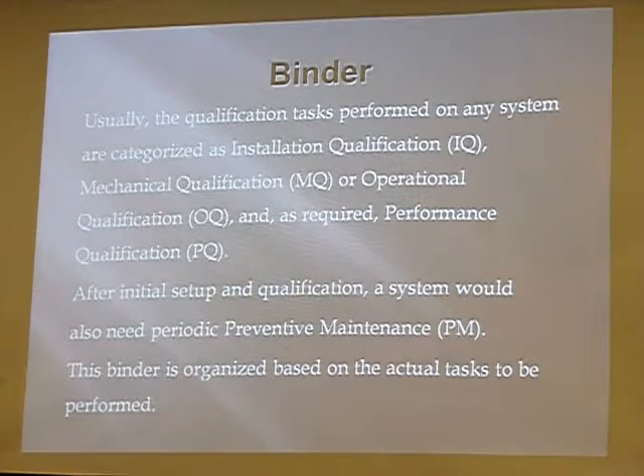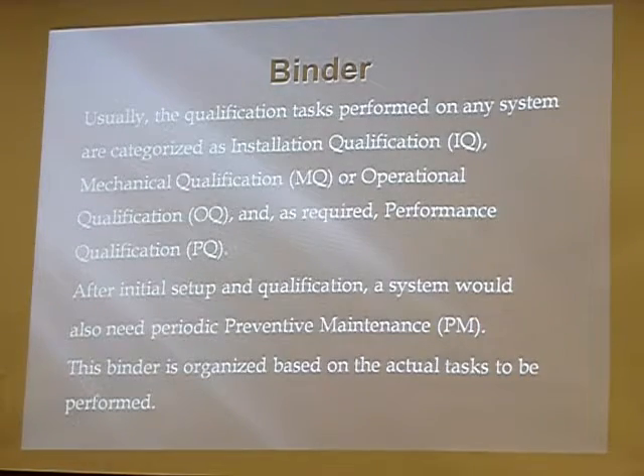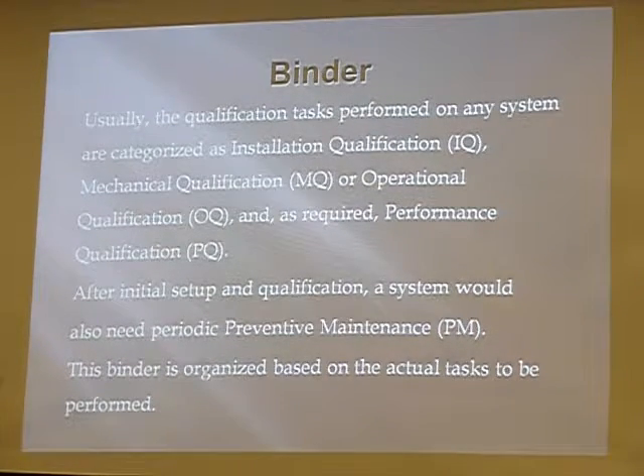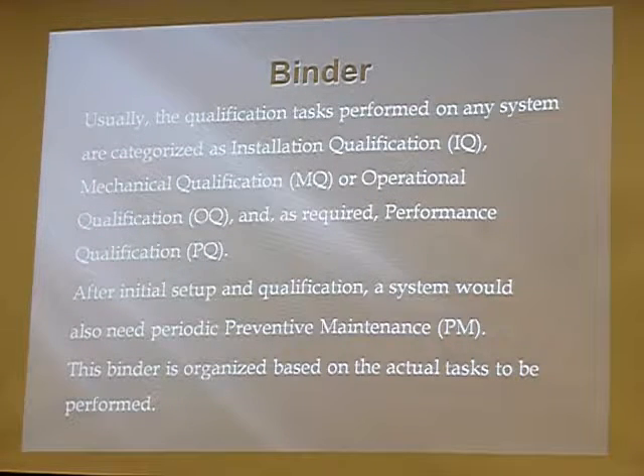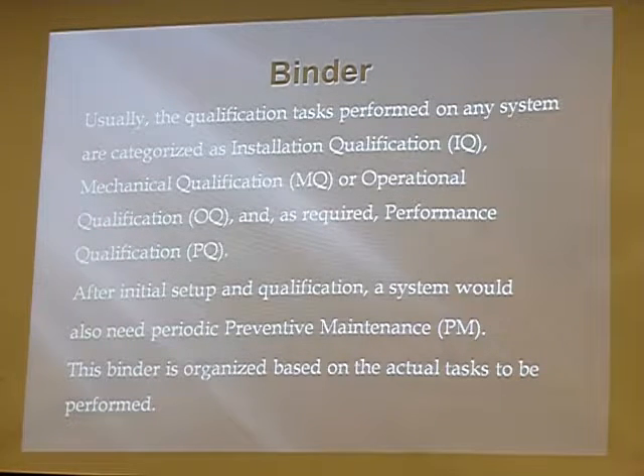When I say MQ, I'm talking about a mechanical qualification on a bath. We only have MQ for the bath. It used to be OQ, but today, in 2015, at Distek, MQ is only specific to a bath, a Distek bath. The reason we did that is because the operational qualification is something that can be measured on our accessory equipment for the bath, which is the auto sampler, the vessel washer, and the easy fill. Those all have OQs, not MQs. They're the same thing. Operational qualification, mechanical qualification.